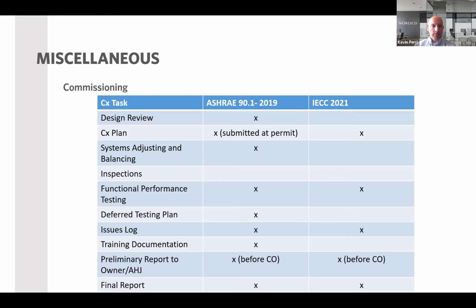System adjusting and balancing needs to happen for ASHRAE 90.1. Inspections need to happen also for ASHRAE 90.1. My table is off here. I'm sorry, there's an X missing there. Inspections need to happen for ASHRAE 90.1, but not IECC. Functional performance testing needs to happen in both pathways. Issues log, both pathways. Preliminary report, final report, both pathways. So differences here are deferred testing plan, training documentation, and your design review. Everything else is pretty much the same, with the exception of maybe having to submit it at a different time.